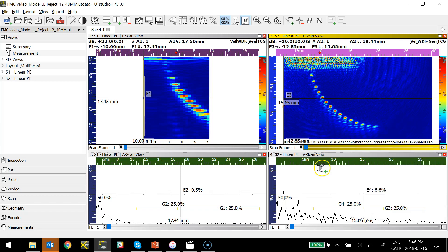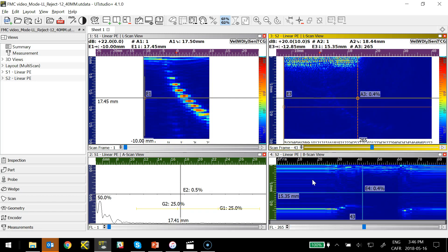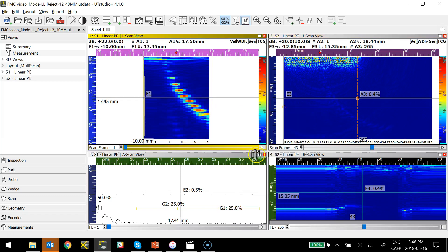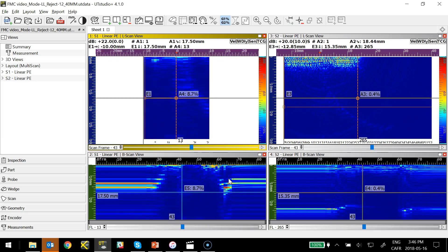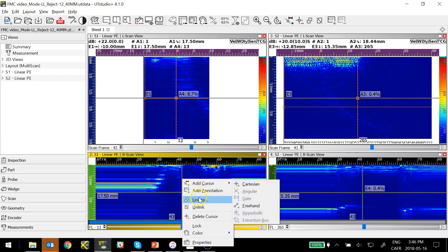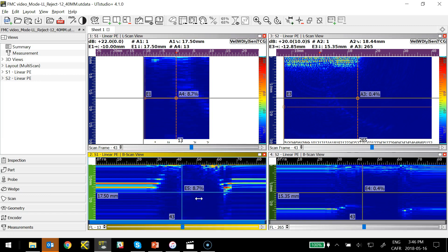Now, an interesting advantage of the Sonatest TFM approach is that all the standard Phased Array tools like B-scan, Top view, End views, all the encoded tools that were available for Phased Array analysis are all available for the TFM analysis.